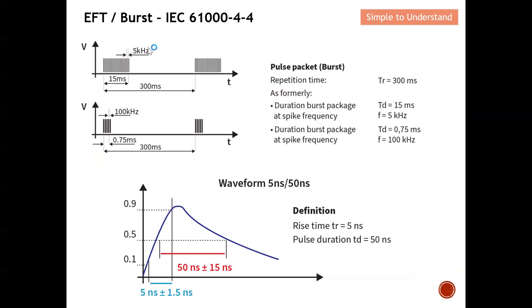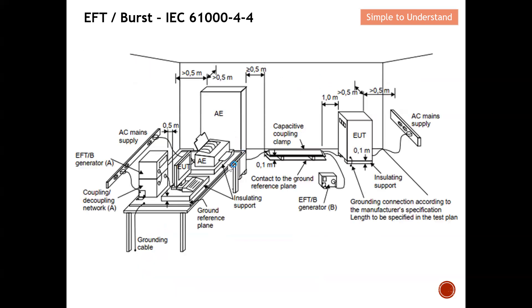To revisit: we have the 5 kHz type and the 100 kHz type. Zooming into one of the pulses, this is what we call the rise time — it needs to be under 5 nanoseconds. We also have the pulse duration of 50 nanoseconds, plus or minus 15 nanoseconds. These pulses are sent in a repetitive manner at either 5 kHz or 100 kHz intervals to test your DUT.